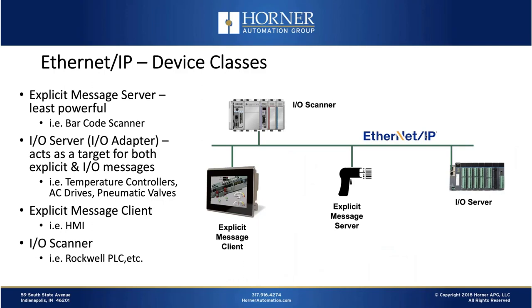There are four different device classes for Ethernet IP, since not all devices are designed to have equal capability. At the lowest level is the explicit message server — these devices act as targets for explicit messages, most commonly seen in simple devices such as barcode readers, RFID readers, or similar. Next is the I/O server, most often called an I/O adapter, which is the most common type of Ethernet IP device. These are not only the target for occasional explicit messages but also for I/O messages. Examples include temperature controllers, variable frequency drives, and more. This is the implementation most often used with our OCS all-in-one controllers. Explicit message clients are less common — they primarily act in an HMI-like capacity to read and write information from other devices using explicit messaging. Our OCS products have some of this capability.